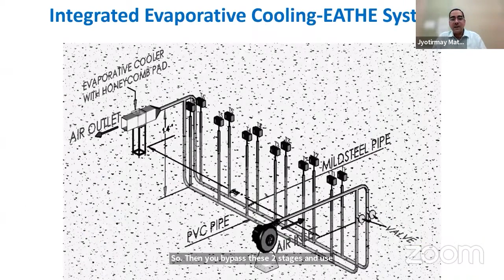So what we did was we tried to integrate our earth air tunnel with the evaporative cooling experimentally. And then what we found was, like shown in this graph, the brown bars are the hours which are comfortable using the earth air tunnel without the evaporative cooler. But as you see, in April, as the ambient temperature increases, the earth air tunnel was not giving sufficient comfort. So I started utilizing the evaporative cooler also. Whatever free cooling I was getting through the tunnel, I got.